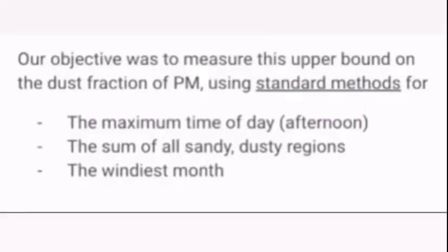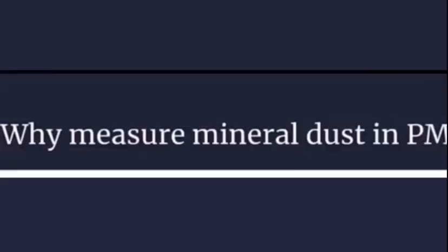And I'll also be talking about the federal reference method, which is known as gravimetric weighing, which is what we had before BAM. Before BAM, you had to collect a filter and you had to weigh it after leaving it for 24 hours at a controlled low humidity of 35%. And that took forever and you couldn't get hourly information. And so BAM has a lot of advantages and it's a federal equivalent method. So why do we need to measure the mineral dust?